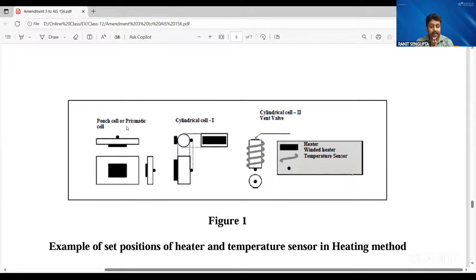If there are cylindrical cells, there is an arrangement given too. If you are using a slim film heater, on one surface we put the heater, and on the other surface we apply the temperature sensor. For cylindrical cells, we can also use winded type heaters, and the temperature sensor is put on the cell vent especially. That is how we have to design the battery pack for the thermal runaway test, or the thermal propagation test.